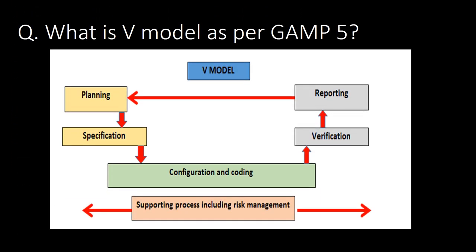What is the V-model as per GAMP-5? Refer to the schematic below for understanding the V-model as per GAMP-5. It starts with planning, then specification, then configuration and coding, then verification, and lastly reporting. From reporting, it may go back to the planning phase, and there will be a continuous support process including risk management throughout.